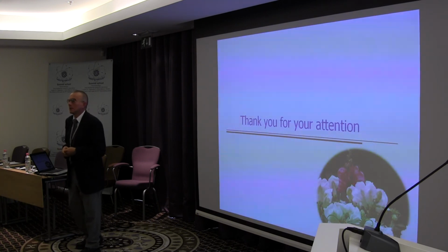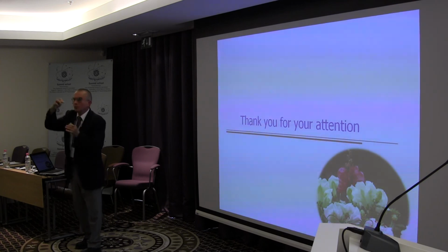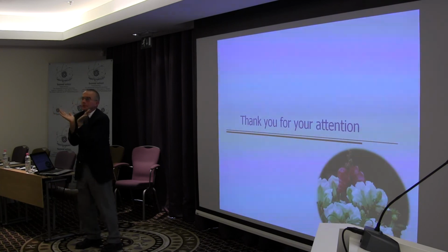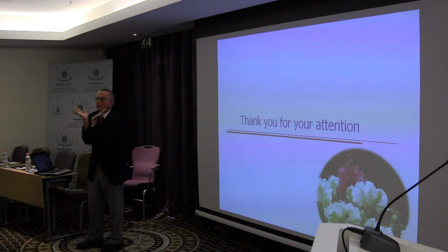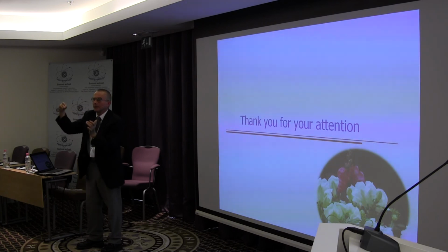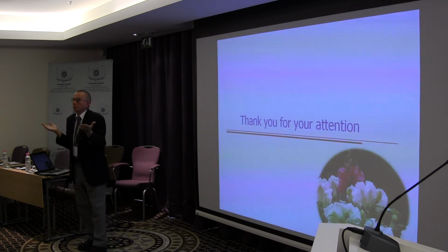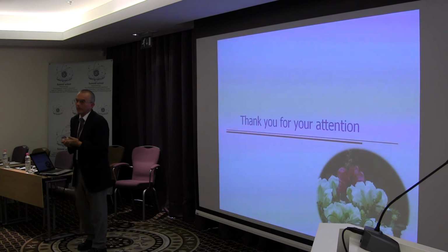How do you calibrate the size of the indenter and the angle of the indenter? You mean the radius or the shape of the tip? We tested using many different cantilevers with many different tips, with many different materials, starting from 5 nanometer radius up to special cantilevers up to some micrometers, for example. So we know exactly what is the effect of the geometry of the tip. We assume that the tip is absolutely stiff, practically. So let's speak again.